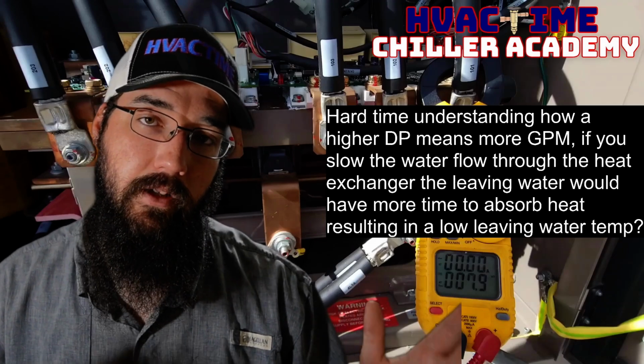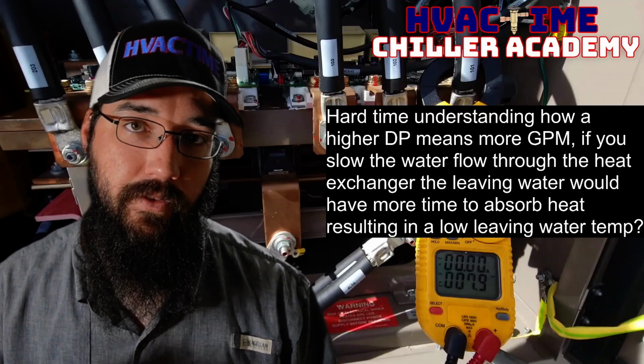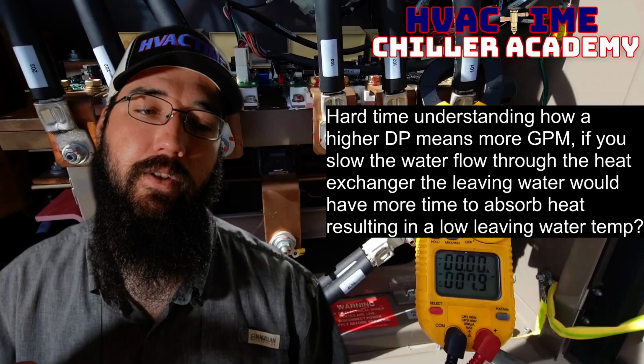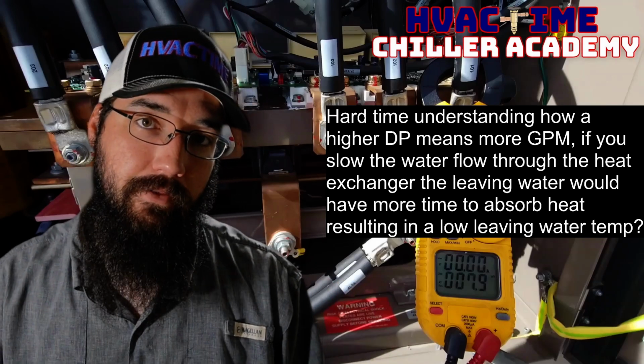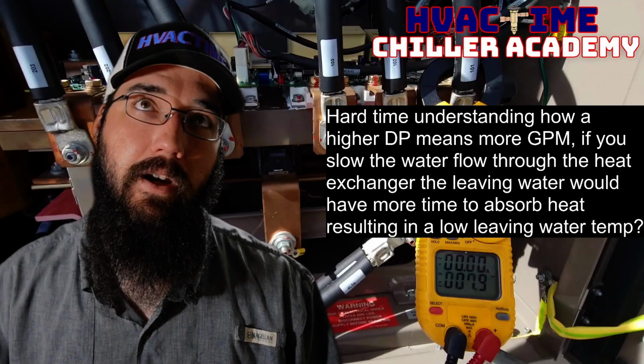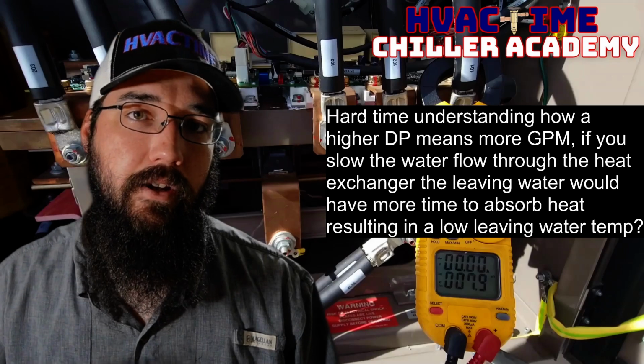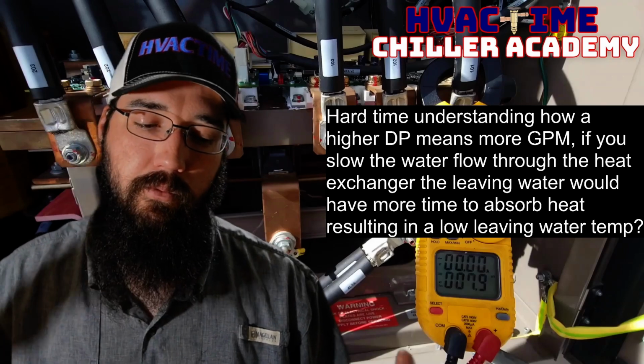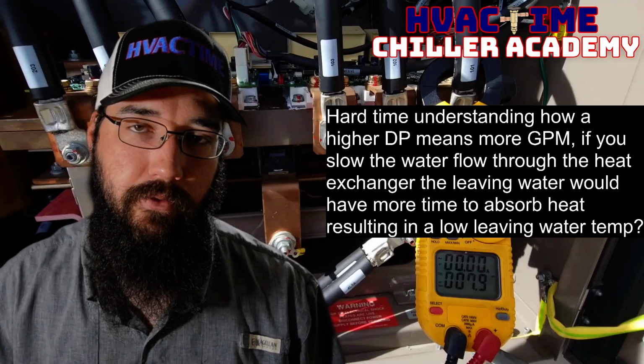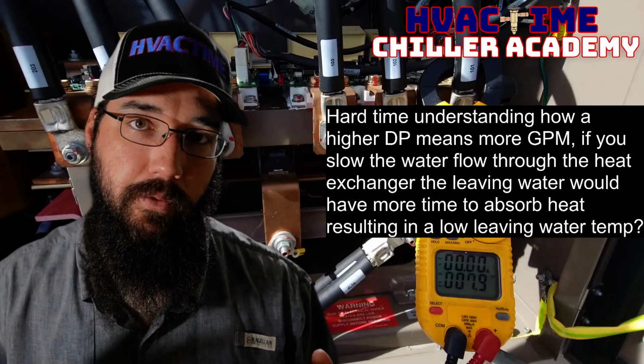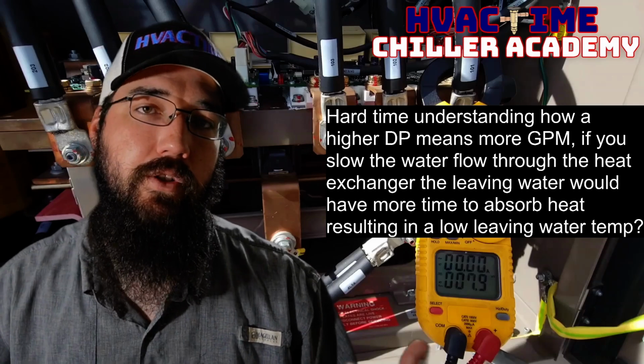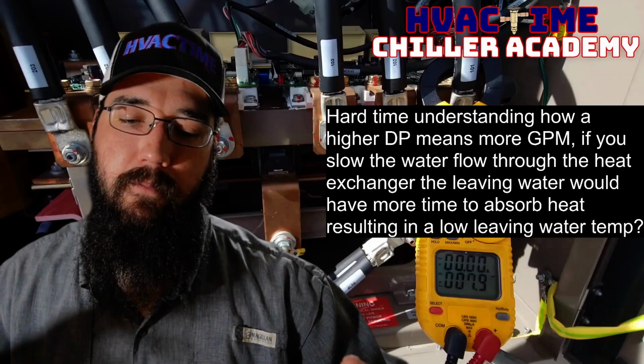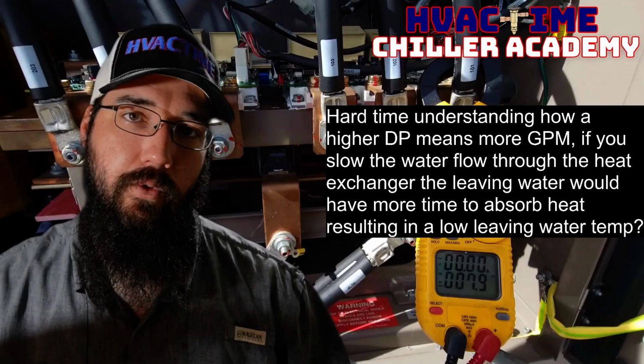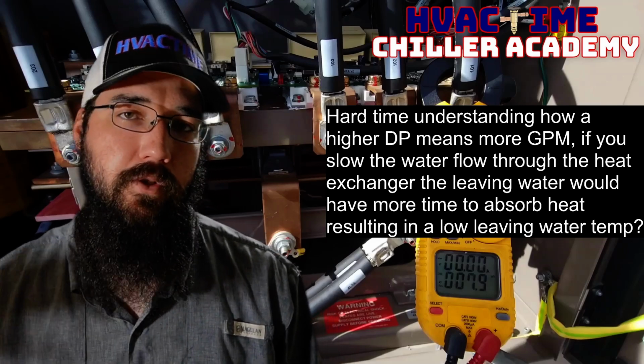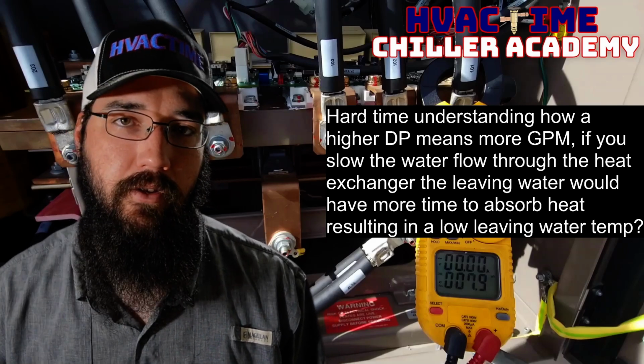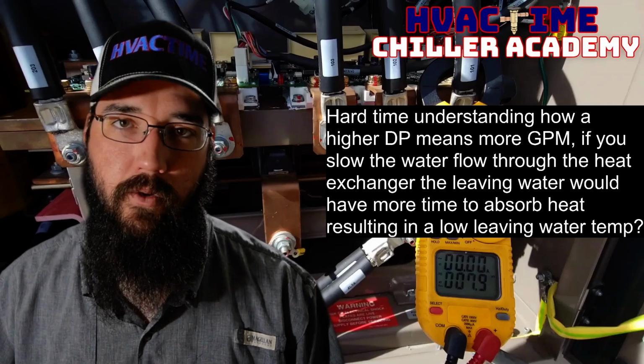The difference between leaving water temperature and refrigerant saturation, specifically evaporator approach in this case. So because we have that higher approach, we're allowing a higher rate of transfer, right? So the bigger the gap, the faster it's going to flow from water to refrigerant in terms of heat, just to achieve leaving water set point. So that would be a high GPM flow, which is not good because then we're just putting way more stress on the machine. That's going to put more stress on our tube bundles, whole bit.